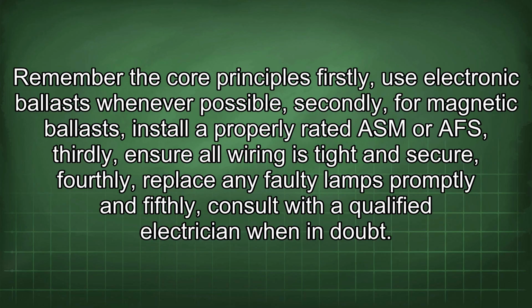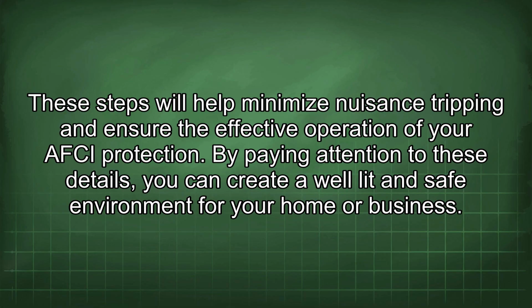Remember the core principles. Firstly, use electronic ballast whenever possible. Secondly, for magnetic ballasts, install a properly rated ASM or AFS. Thirdly, ensure all wiring is tight and secure. Fourthly, replace any faulty lamps promptly. And fifthly, consult with a qualified electrician when in doubt. These steps will help minimize nuisance tripping and ensure the effective operation of your AFCI protection.